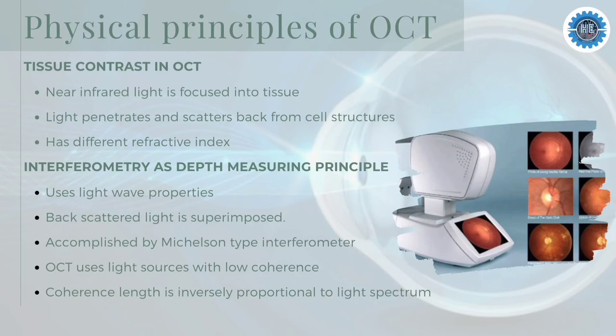The main idea of Optical Coherence Tomography is to use light sources with low coherence. In this case, there is only apparent interference if the two arms of the interferometer are equally long. The coherence length is inversely proportional to the spectrum of the light. Therefore, OCT uses spectrally broad light sources — the broader the spectrum of the light source, the better the axial resolution.